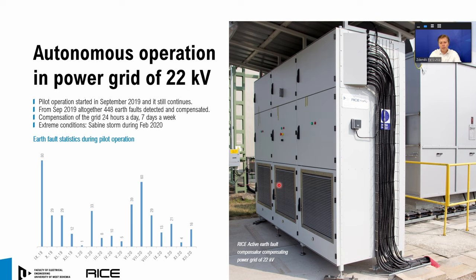In September 2019, we started the autonomous operation of our device in the power grid of 22 kV, so we have already passed almost 2 years of pilot operation of this device in real grid operation. We faced around 500 earth fault strikes, which were detected and successfully compensated. We also had the chance to test our device under extreme conditions, when we faced the Sabine storm in February 2020 in the Czech Republic.